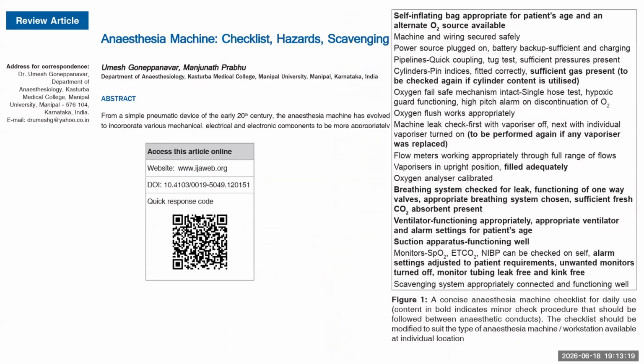So our own Indian Journal of Anaesthesia suggests an anesthesia machine checklist. So we should follow it daily. They mention that a self-inflating bag appropriate for the patient's age and an alternate O2 source should be available. Pipelines, power source, cylinders, all need to be checked. The machine leak check should be performed daily. And again, if you have connected the vaporizer, then you need to perform it again. The breathing system leak should be checked, functioning of one-way valves, and whether sufficient CO2 absorbent is present or not should be checked. The ventilator function. So all this equipment testing needs to be done daily.